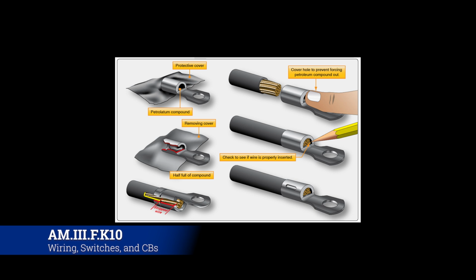Now notice on this, in the bottom left hand corner where it says stripped wire, that lug has a shoulder on it. That shoulder is meant to go over the insulation, so that the exposed wire - your stripped wire - is covered totally inside of the terminal lug.